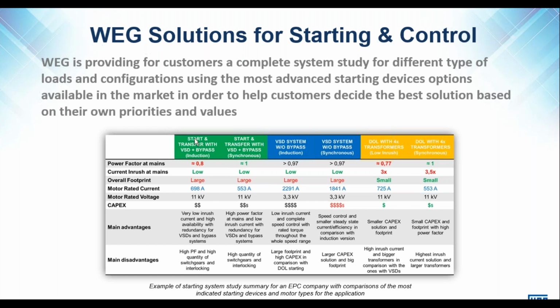Okay, then just to summarize, we look at some parameters for the different starting methods that we've discussed. So when we start and transfer with the VSD and bypass, our power factor is approximately 0.8. We have a very low inrush current at the mains.